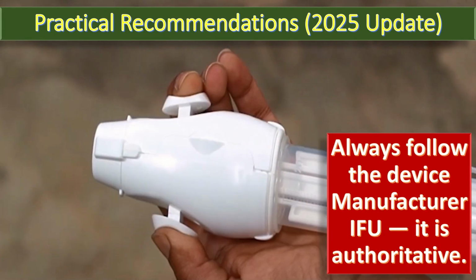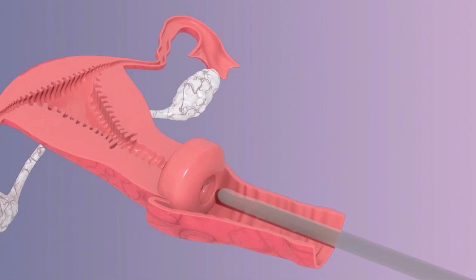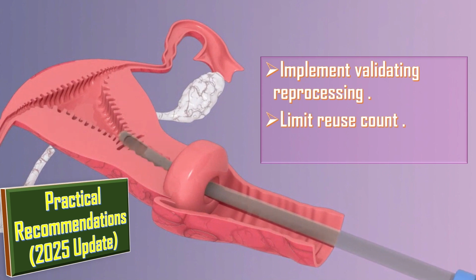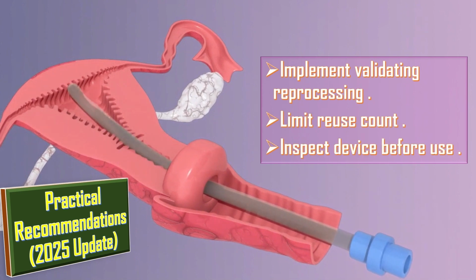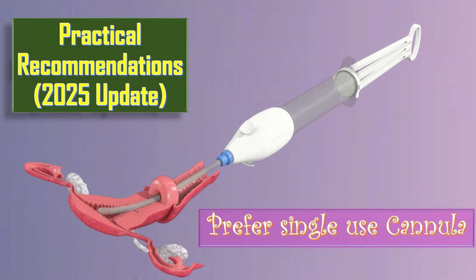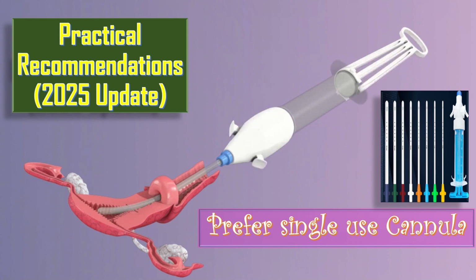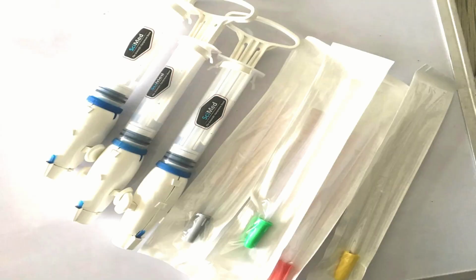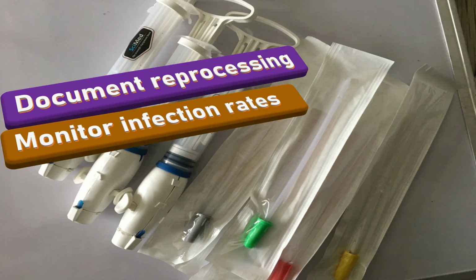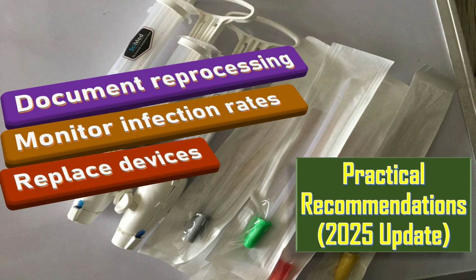Where the IFU allows reuse, implement validated reprocessing, limit reuse count per validated data, and inspect devices before each use. Prefer single-use cannulae unless the device is specifically validated for reuse. If reuse is unavoidable due to supply constraints, document reprocessing, monitor infection rate, and replace the device at the first sign of wear.